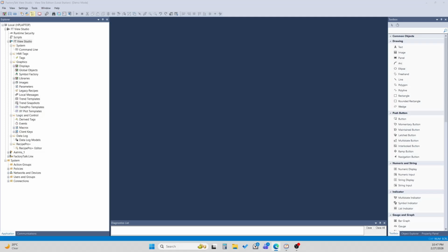When you are developing a FactoryTalk View system, log on to either the network directory or a local directory. Create an application with a device server, a data server, and optional alarm and event servers. It means when you create any project in FactoryTalk View Studio, the application and devices will be stored inside the FactoryTalk View directory, but the data server and alarm server are optional.